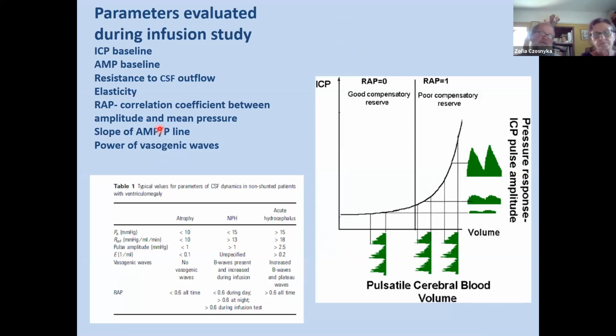Which parameters do we evaluate during an infusion study? This is baseline ICP, pulse amplitude at the baseline, resistance to CSF outflow, elasticity, once again RAP, the correlation coefficient between amplitude and mean pressure. This is the interpretation here, where we have the linear relationship between pressure and volume on the pressure volume curve. RAP is 0, this is good compensatory reserve, and RAP equal to 1 is where we are switching to the exponential part of the pressure volume curve, and the compensatory reserve is poor. And then we also calculate the slope of the amplitude pressure line and the power of vasogenic waves.